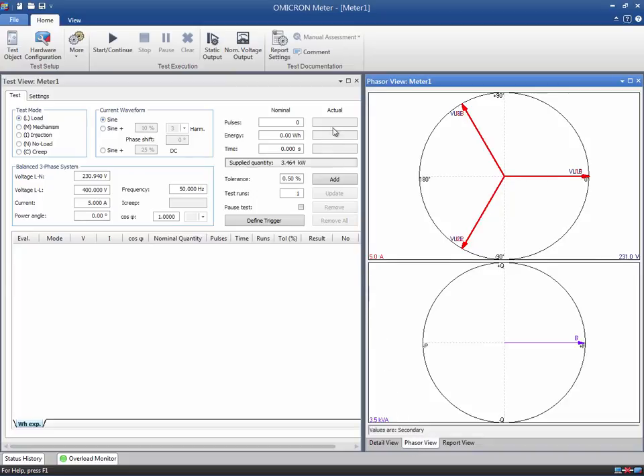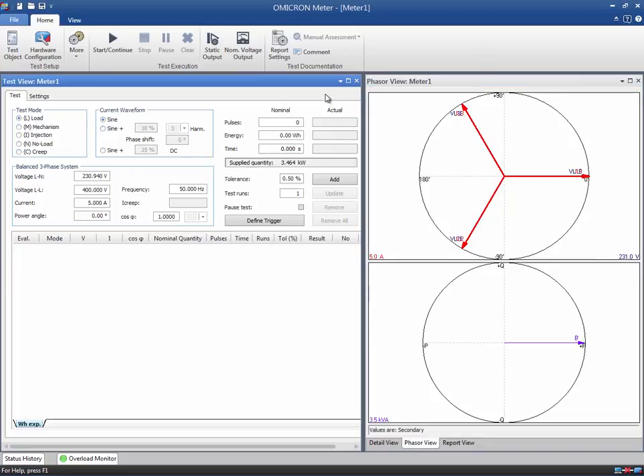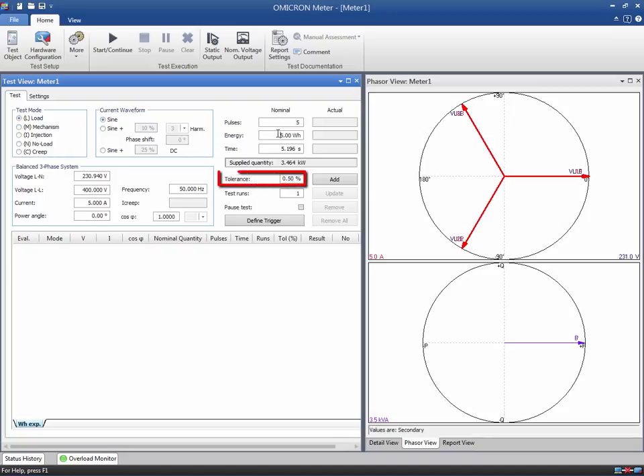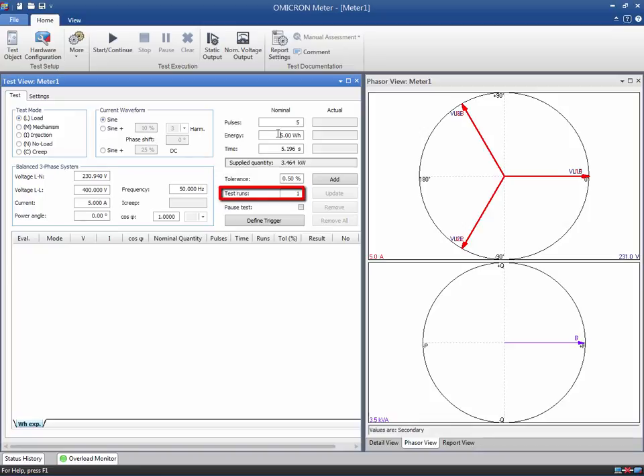Now, you only have to define the test itself by entering one of the nominal values, that is, the total amount of pulses, the energy to be injected, or the test time. For example, we enter five pulses. The energy and total time are calculated automatically. The tolerance is set by default to the meters class specified in the test object. The number of test runs specifies how often the selected line of the test table is executed.